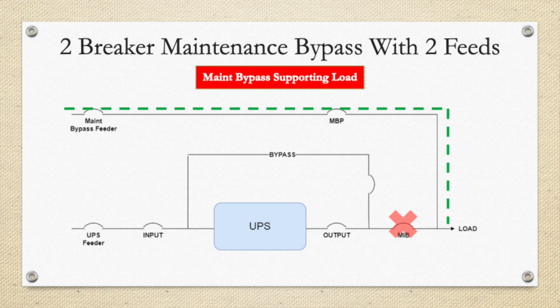Next drawing shows the 2-breaker with 2 feeds to it and running in the maintenance bypass mode. Under this configuration, we can totally de-energize the UPS, and since it's fed from a separate breaker, if we had to put a load bank or load test this UPS while maintaining your critical load on the maintenance bypass feeder, we can do that. So the shortfall in this configuration is there is a potential for operator error because you have to remember to transfer the system to internal bypass before transferring to maintenance bypass.